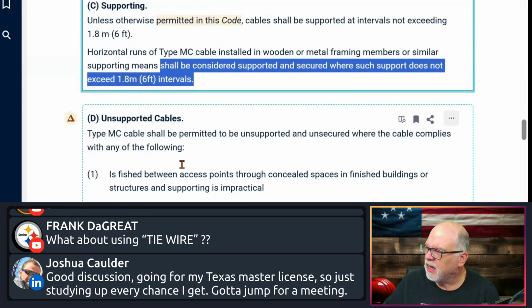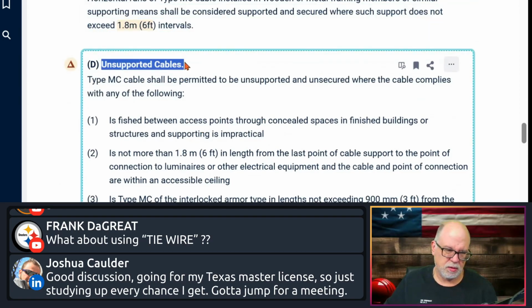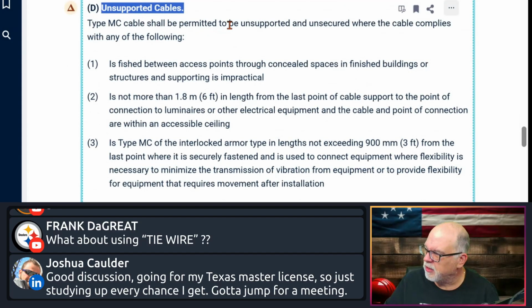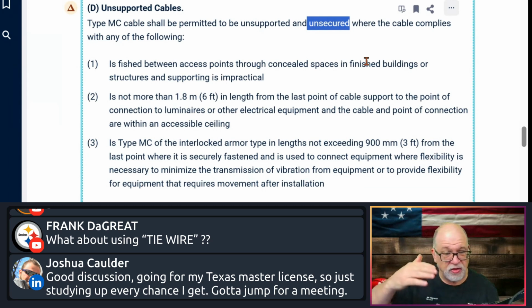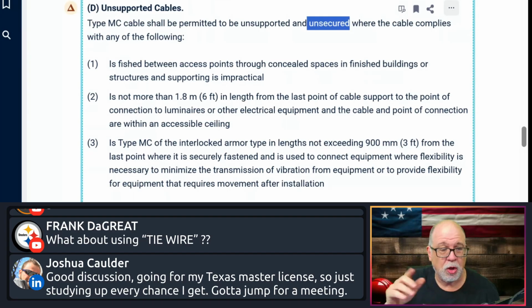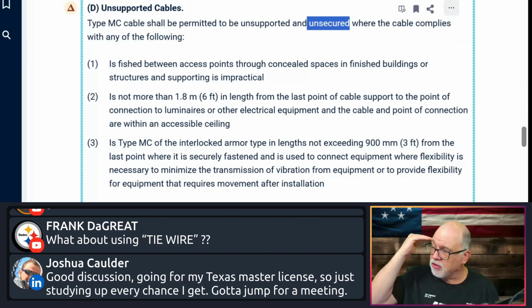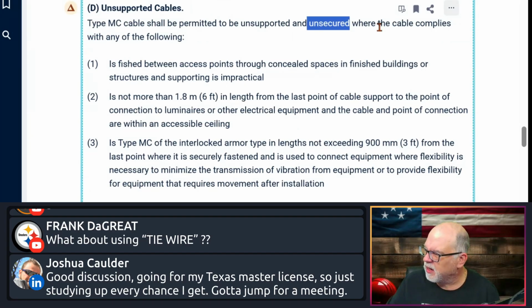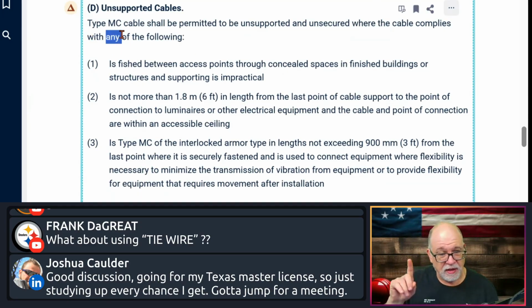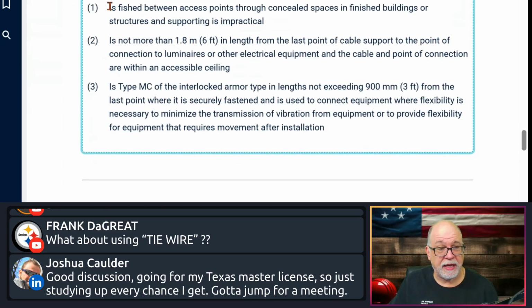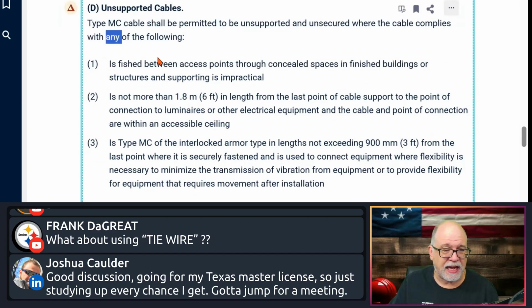Now, here is the unsupported cable. When can I run it unsupported? Well, it says MC cable shall be permitted to be unsupported and unsecured. Okay, that 6 foot, 6 foot thing you remember when it comes to MC. By the way, AC cable is 4.5 feet. It's just like non-metallic sheathed cable when it comes to supporting it. So unsupporting MC cable, it says, okay, I can do that where the cable complies with any, not all of these, any of these. Okay. Number one, what if it's a finished building and I'm coming back and I'm called back because I got to fish something in the wall?